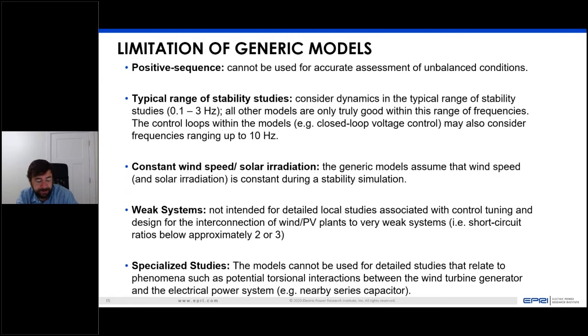There are limitations. Right now they're only positive sequence, even though we're starting to look at developing generic models for other types of tools as well. They're mostly good for stability studies, that 0.1 to 3 hertz range. If you really want to look at some control loop issues, you might need a different type of model, a more detailed PSCAD or EMTP type model.